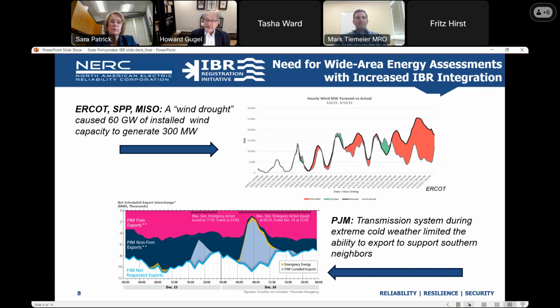The other thing we're seeing, shown in the bottom chart, is that transmission is becoming more of a concern. During one of the winter storms out east a couple years ago, there were times when we had excess capacity in one part of the system, PJM, and a generation deficit outside of that, either in the MISO area or down in the southern parts of the country, where that generation couldn't get out because of transmission limitations. So one thing NERC is looking at, and we've also been directed to do by Congress, is interregional transfer capability - what kind of transmission needs to be put in place so generation can be transferred across the system when there's excess in one area and need in another.